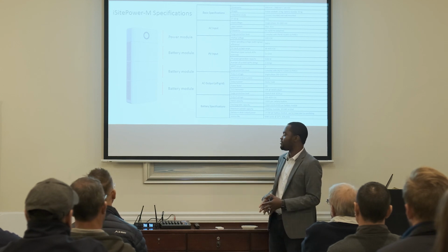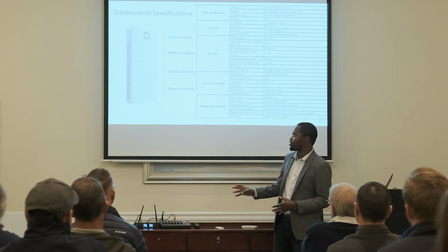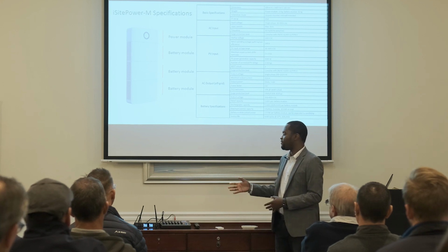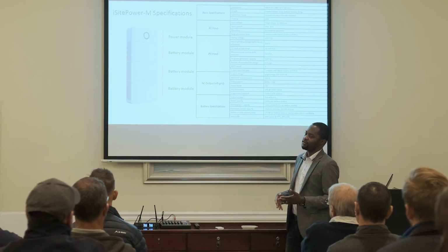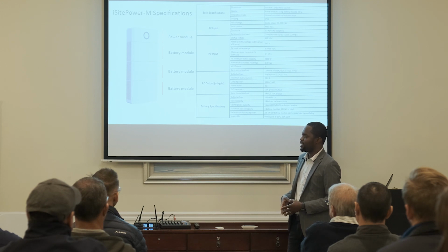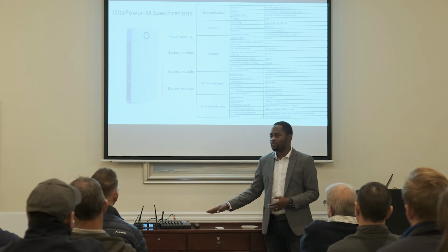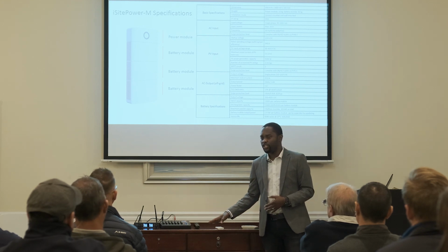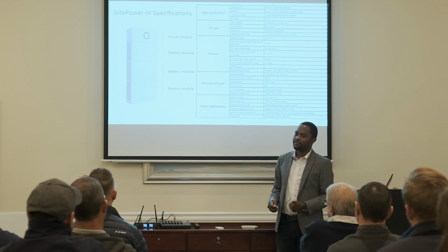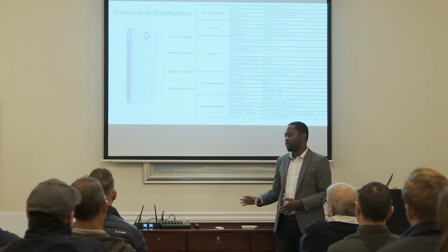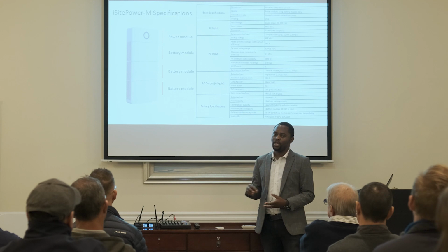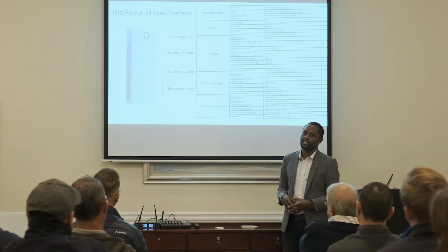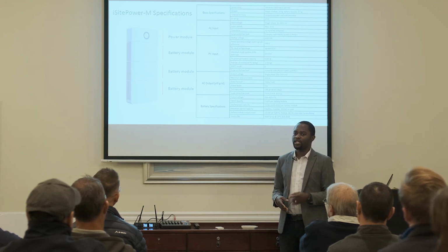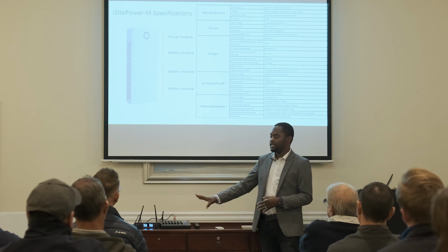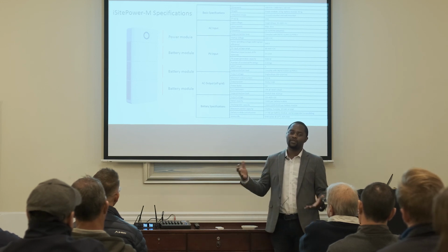I would not want to repeat what Raf has already covered, but just to add a little bit on that. It's a 6 kVA operating at 0.833 power factor. That gives you a 5 kilowatt inverter. The batteries are 5 kilowatt-hour modules each, right? But it's 0.5 C. So what it means is that from your 5 kilowatt-hour, you can only take 2.5 kilowatt at a time. So we strongly recommend that you have at least 2 batteries to get the maximum power out of it.